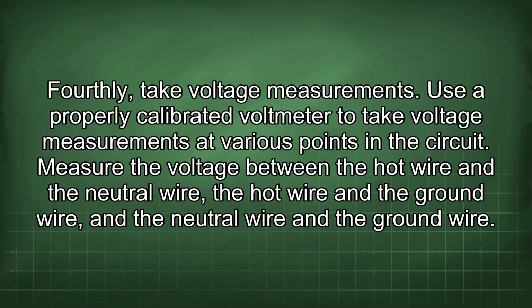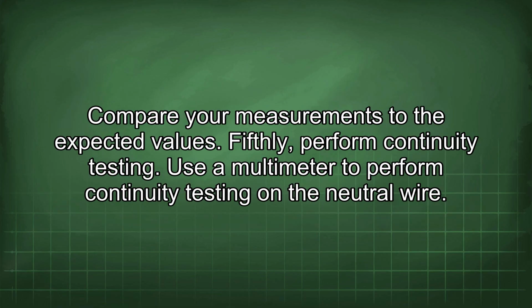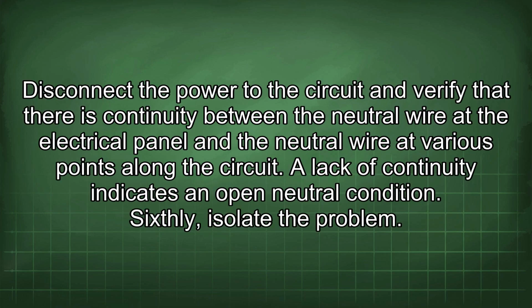Fourthly, take voltage measurements. Use a properly calibrated voltmeter to take voltage measurements at various points in the circuit. Measure the voltage between the hot wire and the neutral wire, the hot wire and the ground wire, and the neutral wire and the ground wire. Compare your measurements to the expected values. Fifthly, perform continuity testing. Use a multimeter to perform continuity testing on the neutral wire. Disconnect the power to the circuit and verify that there is continuity between the neutral wire at the electrical panel and the neutral wire at various points along the circuit. A lack of continuity indicates an open neutral condition.